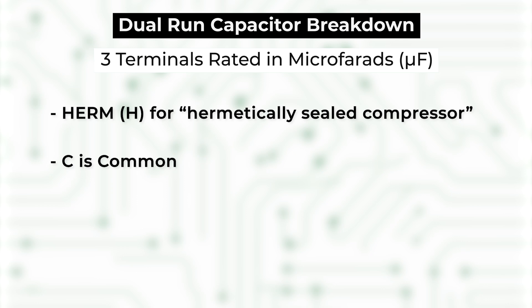A dual run capacitor has three terminals, and it's rated in microfarads. Here's the quick breakdown. HERM, or sometimes just H, stands for Hermetically Sealed Compressor. This terminal on the capacitor connects to the compressor's run winding, and typically has a higher microfarad rating. C is common, and fan is for the fan motor.